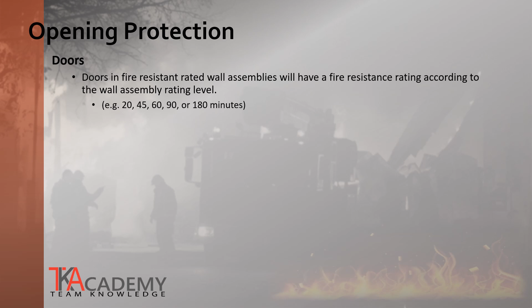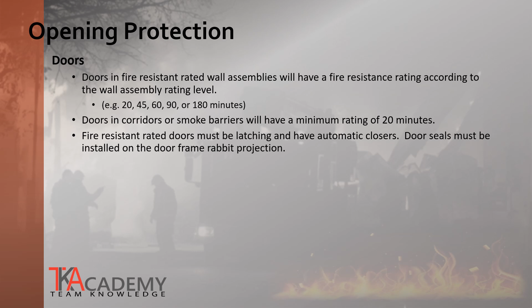Doors within corridors or smoke barriers will have a minimum rating of at least 20 minutes. Fire-resistant rated doors must be latching and have automatic closers. Door seals must be installed on the door frame to keep the transmission of smoke from passing through the door opening. Fire-resistant rated doors must have a factory label affixed that indicates the rating level. This label is typically placed on the hinge side of the door edge.